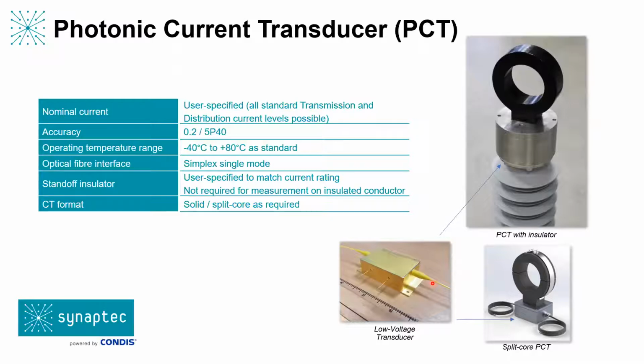And on the electrical side, we have the CT for around the primary current, or if we want to measure the secondary current, we can provide modules that connect directly to the secondary of existing CTs, or are installed in the bay cabinets in a substation, for example, that read the secondary currents from existing CTs, but they operate passively and they take the secondary current and convert it into our optical signal. So for all of our sensors, there is always a conversion from the electrical domain to the optical domain. There is always only a single fiber connection and an optional fiber output to take it to the next sensor, because you can daisy chain them. And the connection of the primary or secondary connected devices is exactly the same as would be with traditional CTs and VTs or traditional merging units, except that you do not need to have any power or time sync on those devices.